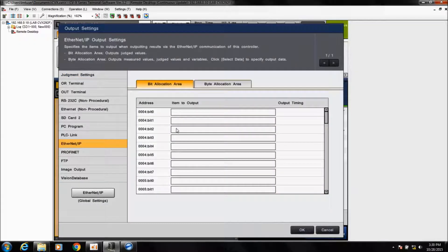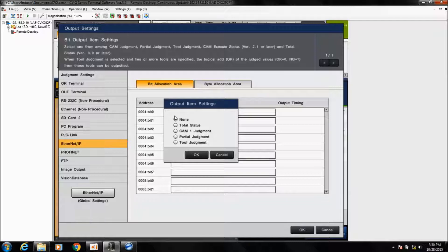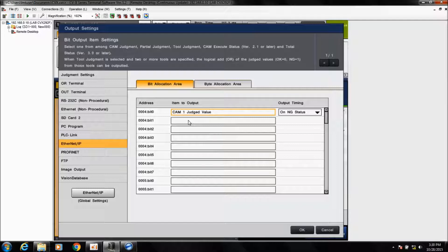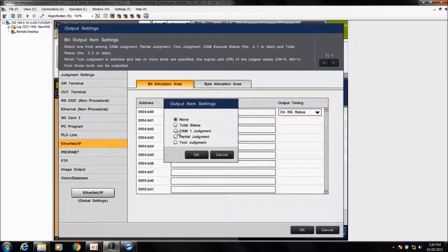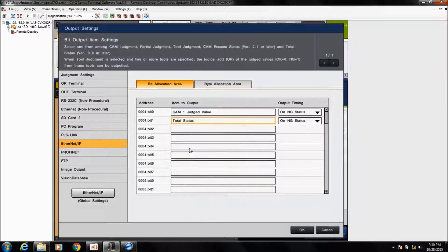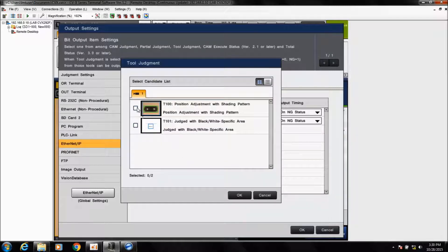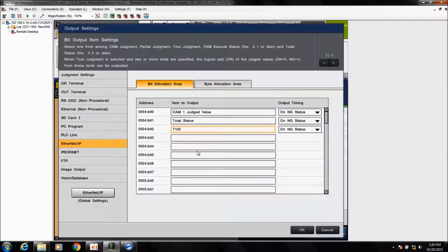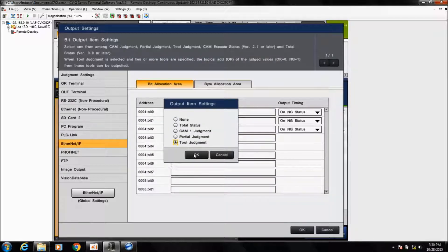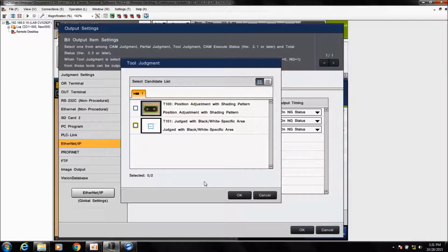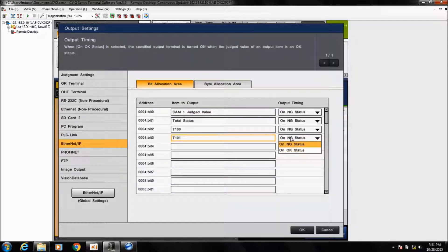The bit allocation area is the status bit area — pass/fail results. You can output tool results and camera judgments by adding them to the list. Click the bit number, choose camera status, total status, or individual tool judgments by selecting the tool. These are your simple OK/No Good outputs, and you can choose whether a one represents OK or No Good. You have 64 of these bit allocations to set up.